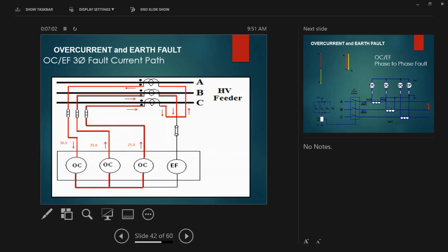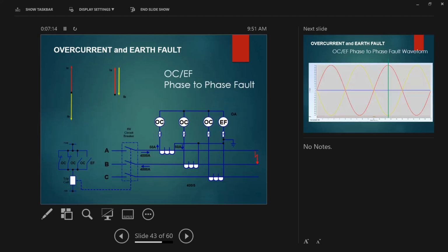Now, the primary side is the same. So 50 amps, 25, 25. Same, there will be no flow of current on the coil of the earth fault because your angle is maintained. Now, what if you have a single phase fault? Now it's not balanced anymore, isn't it? Because you have a fault here. Because the angles are pulling against each other, opposite to each other, there will be no stray current on the neutral. So still you don't have flow of current on the earth fault because the two opposing currents will cancel out on this loop, on this area here.